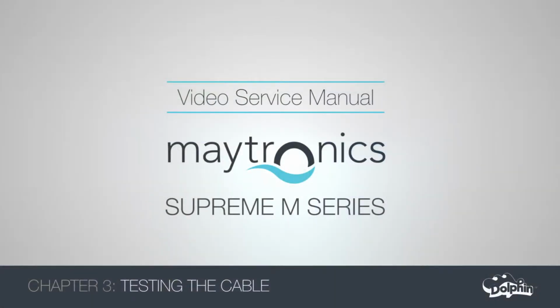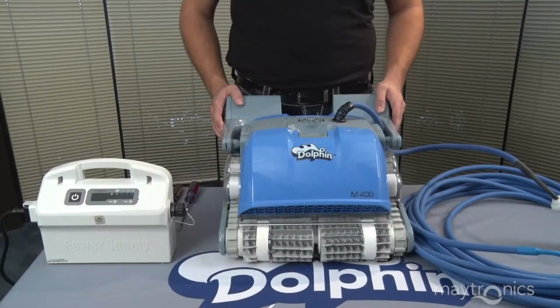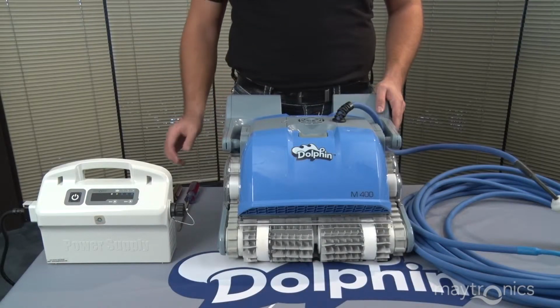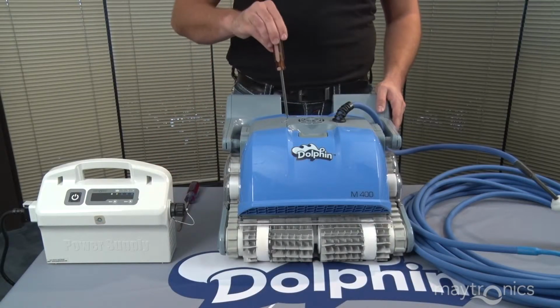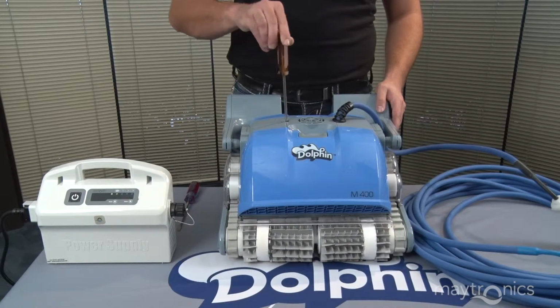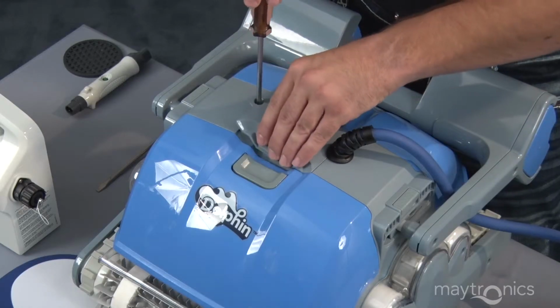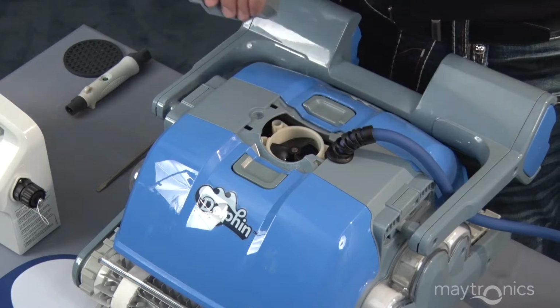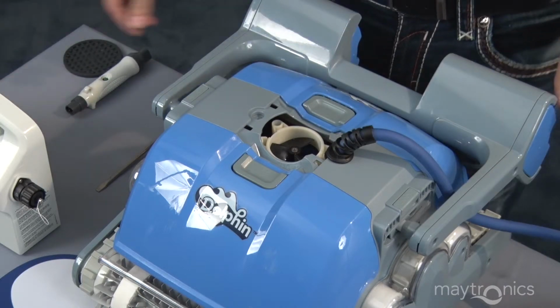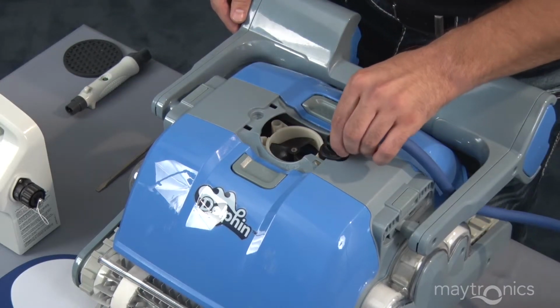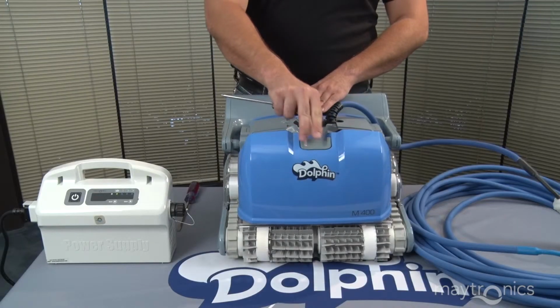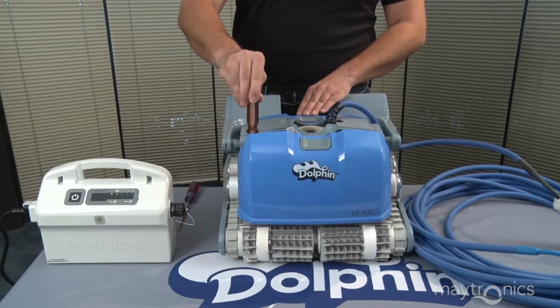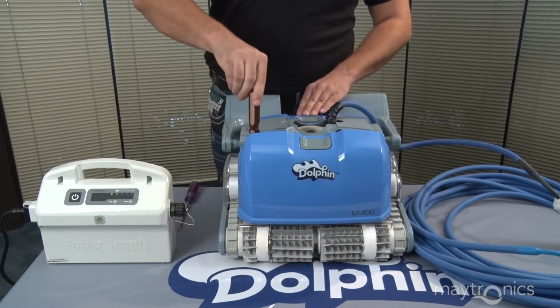Chapter 3. Next, we will test the cable. Begin by removing the screw holding the impeller cover in place. Then remove the impeller cover. Dislodge the rubber strain relief grommet from its notch. Next, remove the 4 screws securing the shell of the unit to the chassis. 2 are located under each cartridge door.